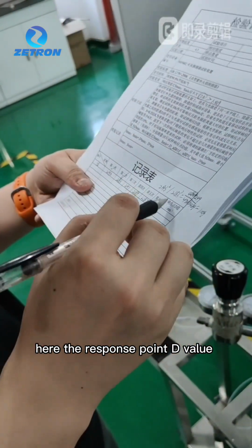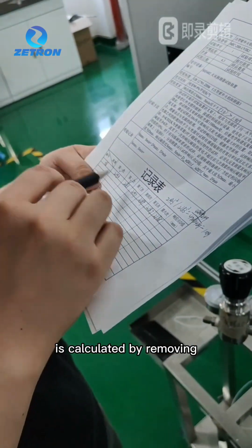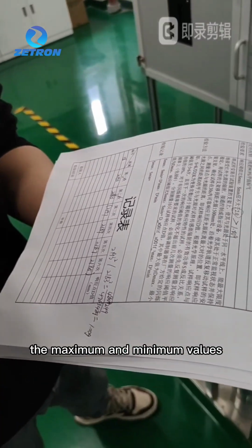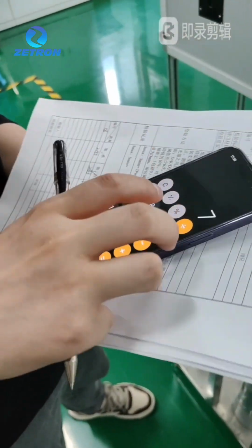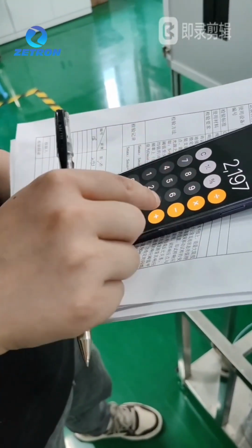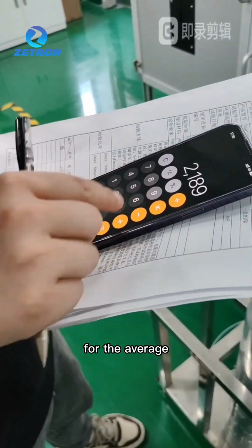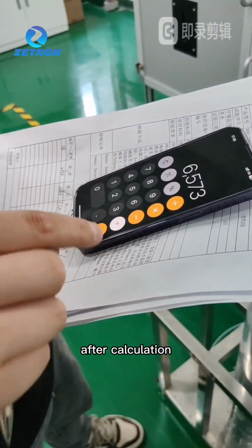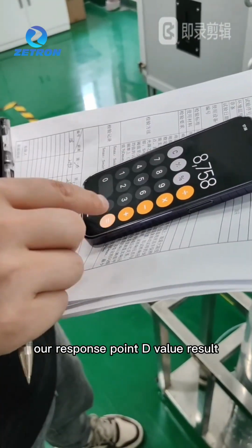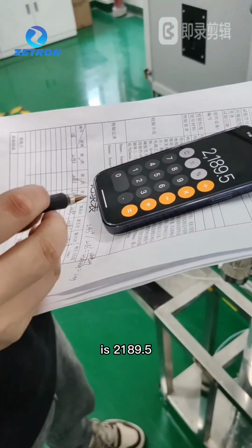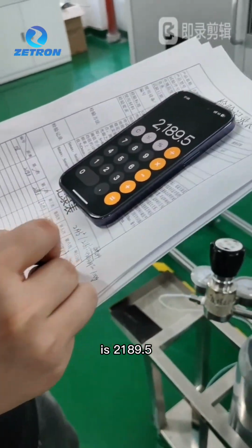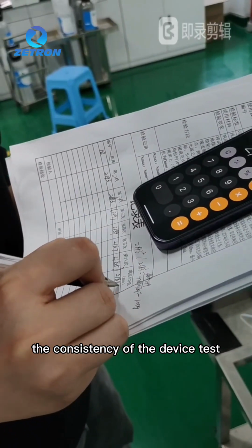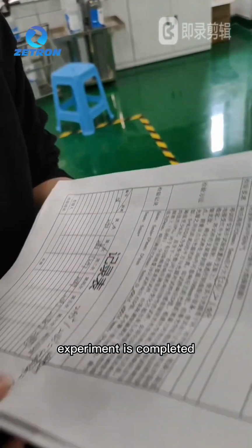Here the response point D value is calculated by removing the maximum and minimum values, then taking the average of the remaining 4 values. After calculation, our response point D value result is 2189.5. The consistency test of the device is completed.